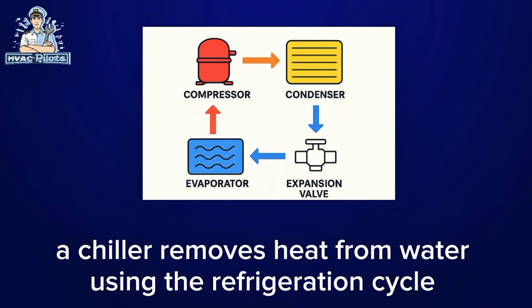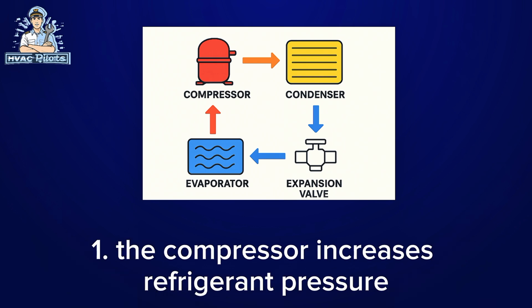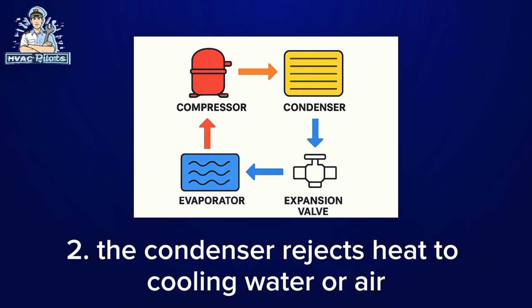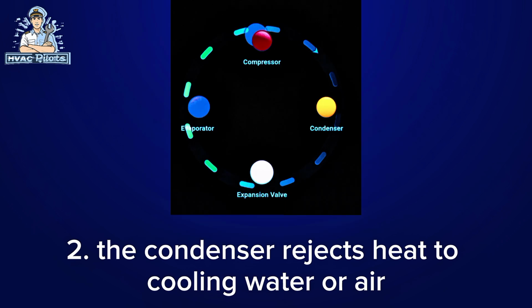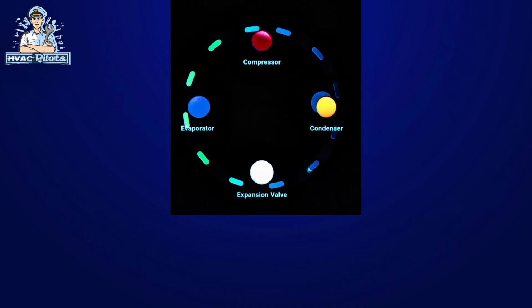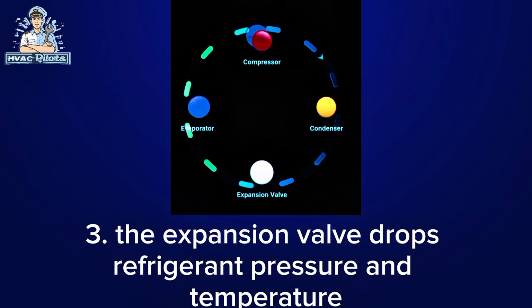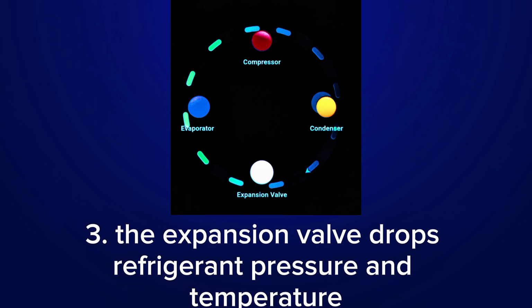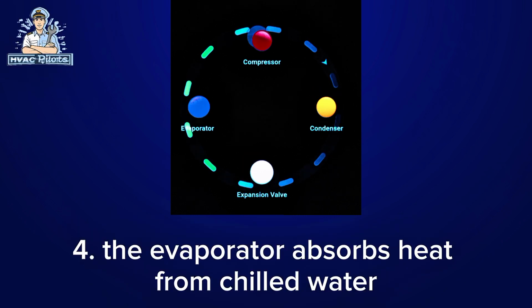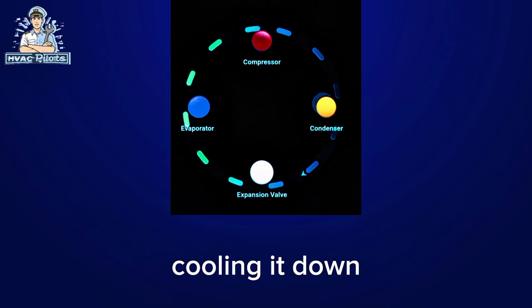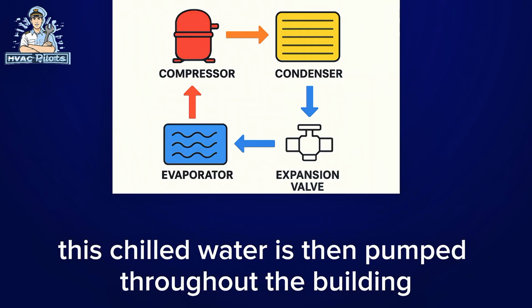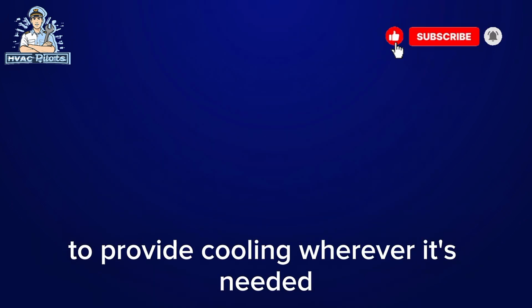A chiller removes heat from water using the refrigeration cycle. 1. The compressor increases refrigerant pressure. 2. The condenser rejects heat to cooling water or air. 3. The expansion valve drops refrigerant pressure and temperature. 4. The evaporator absorbs heat from chilled water, cooling it down. This chilled water is then pumped throughout the building to provide cooling wherever it's needed.